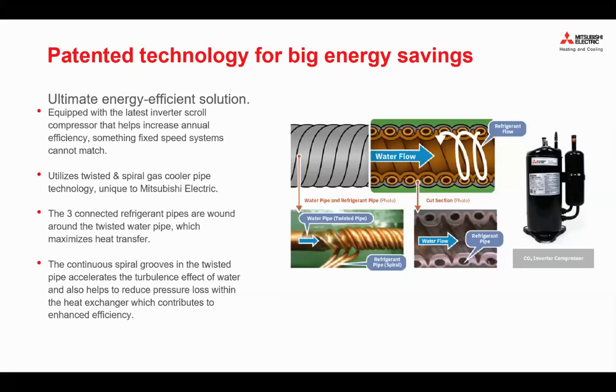So why are we using the gas cooler? Because scale will grow when cold water is heated. The gas cooler uses a larger diameter water pipe, so scale accumulated on the pipe is less likely to result in clogging. And because CO2 also operates at a higher pressure, round refrigerant piping with a thick wall would increase the internal pressure, which may result in lower efficiency. Therefore, we introduced the twisted pipe around the water piping with spiral piping. This increases the contact area between the refrigerant piping and the hydronic piping, and it also improves efficiency while reducing the product size.